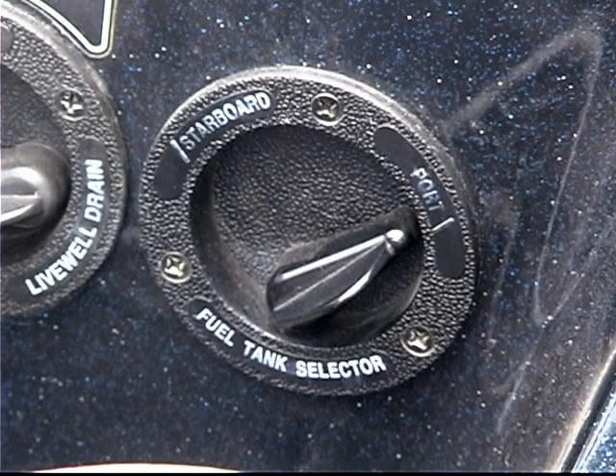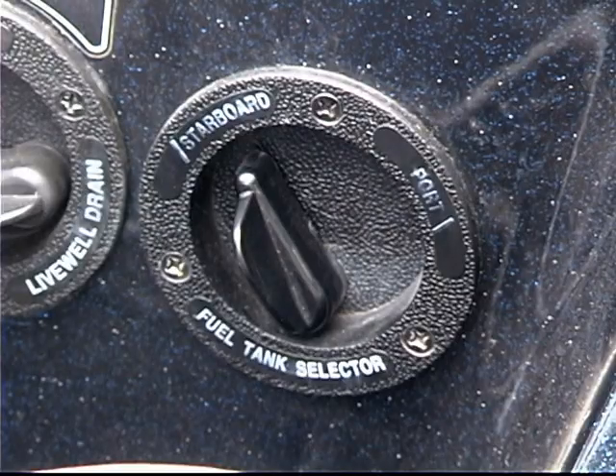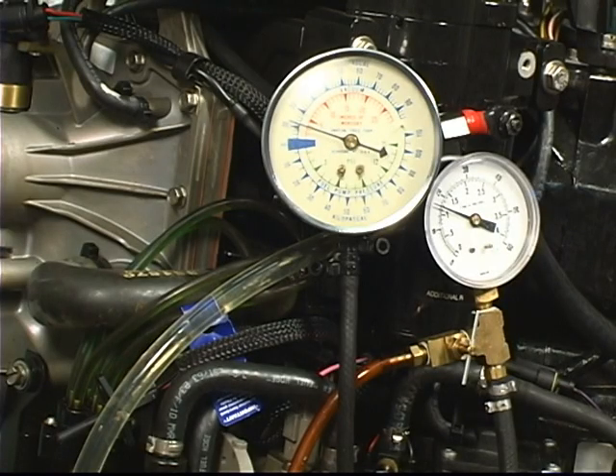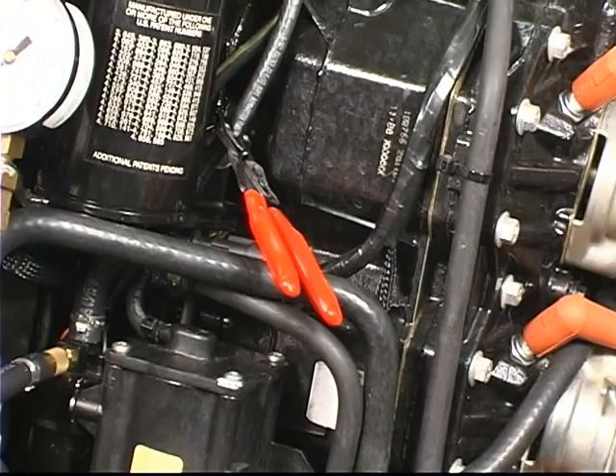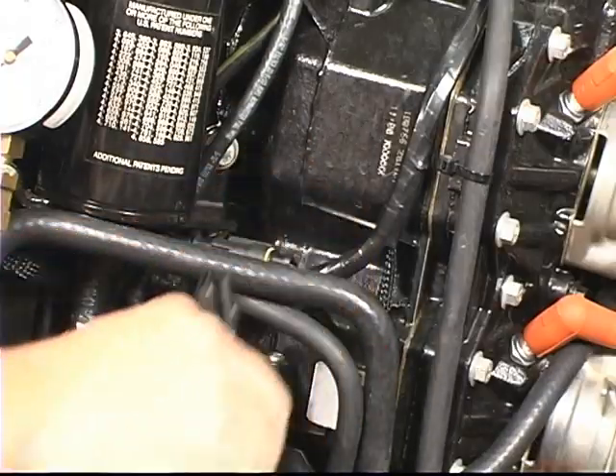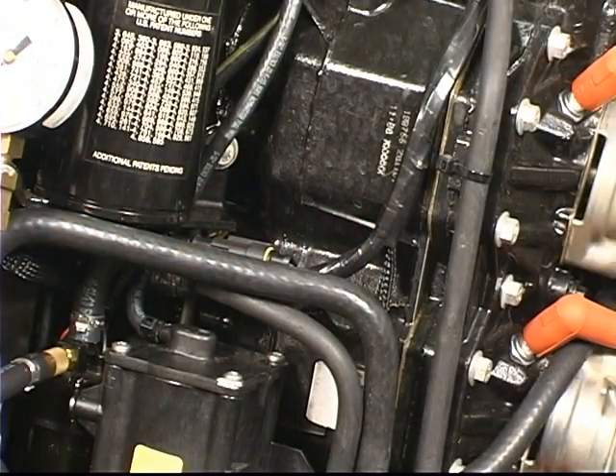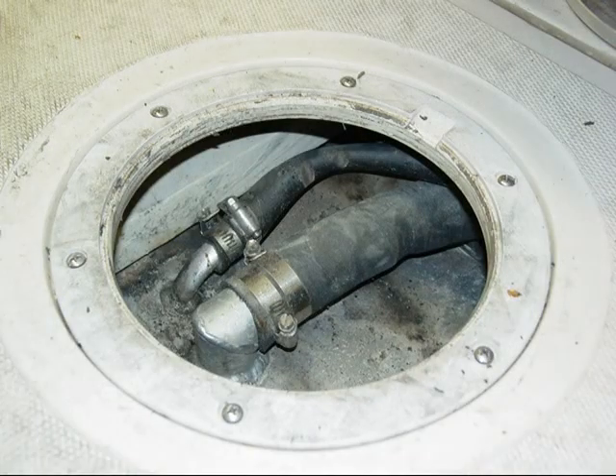For boats with multiple fuel tanks, set the fuel selector valve to the next fuel tank. Repeat steps 1 through 9 in the fuel flow test instructions for each fuel tank in the boat. When you're done, remove the hose pincer from the vapor separator vent hose. This test does not confirm the operation of fuel tank venting. Check fuel tank vents for blockage and fuel tank vent hoses for restrictions.